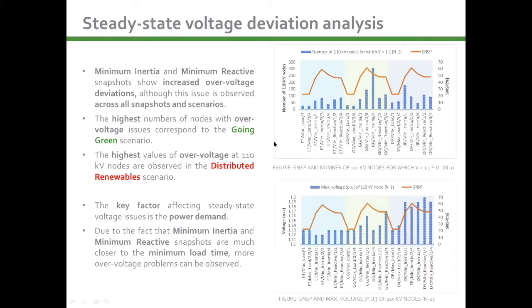Over voltage deviation analysis shows a similar trend to the observation made on the previous slide. As you can observe from the figures, there is a significant correlation between the problems with high voltage and higher levels of renewables, especially for the going green and distributed renewables scenarios. Minimum inertia and minimum reactive snapshots show increased over voltage deviations, although this issue is observed across all snapshots and all scenarios.